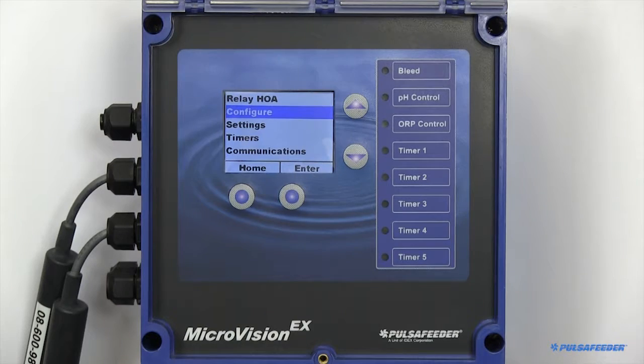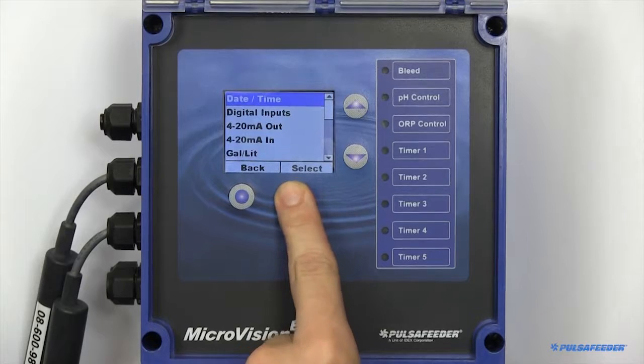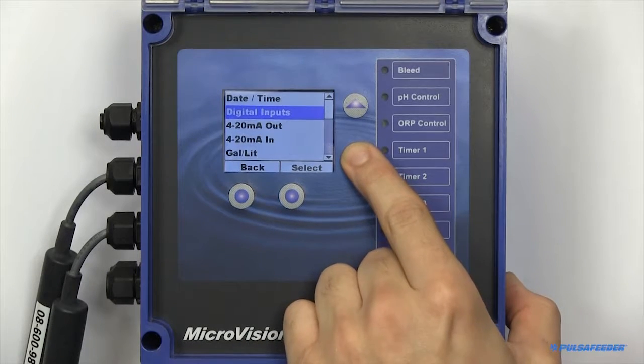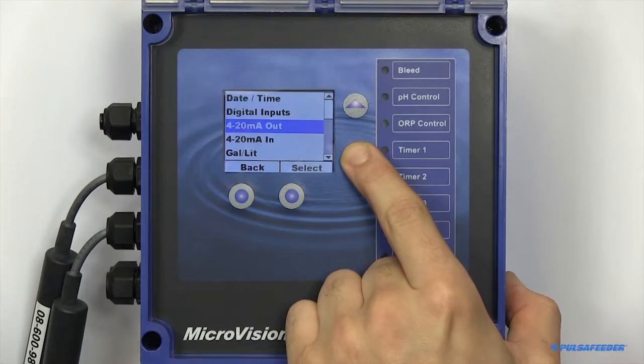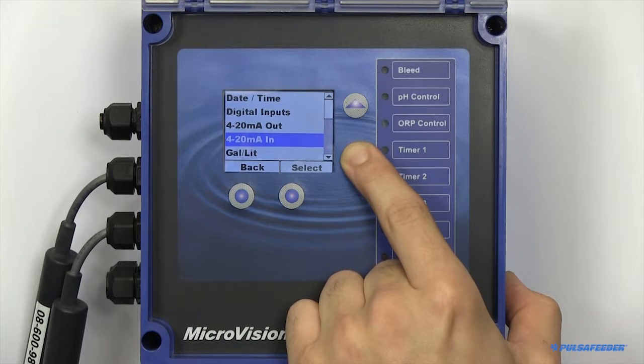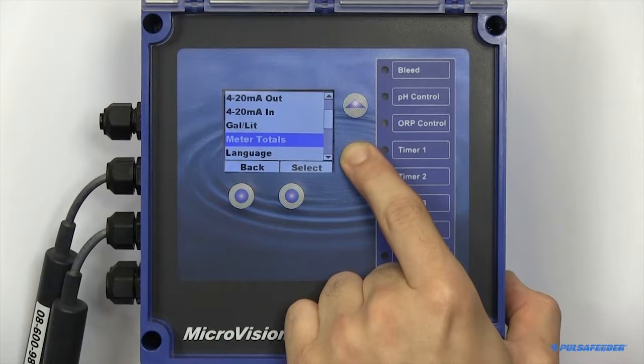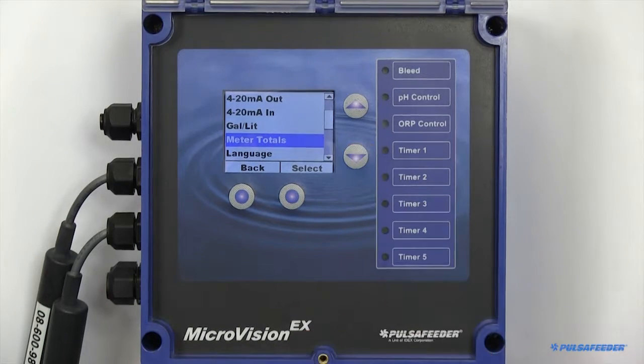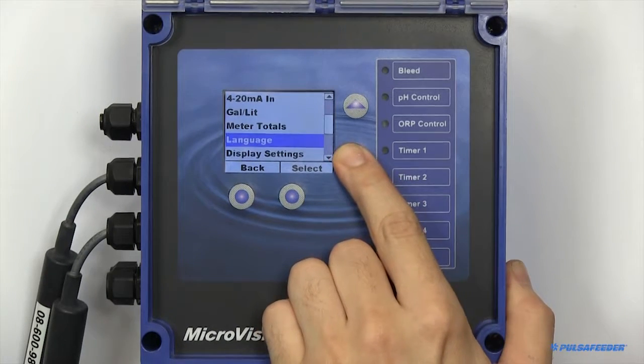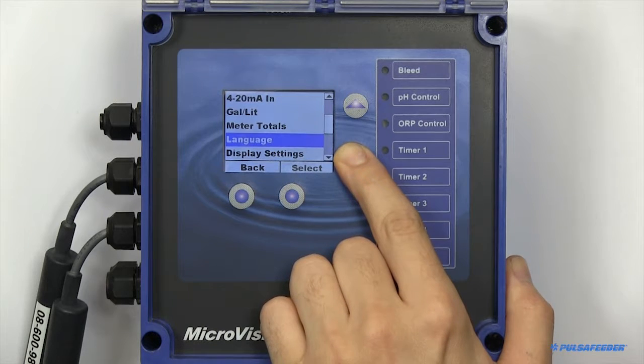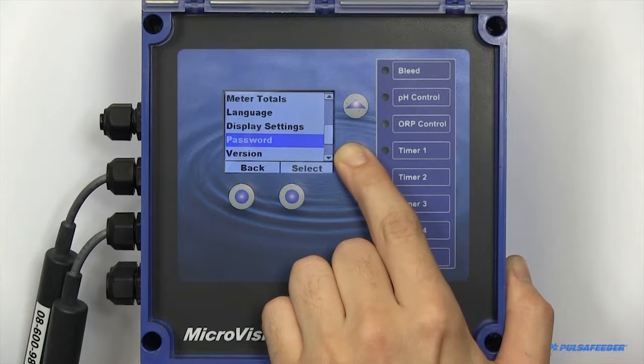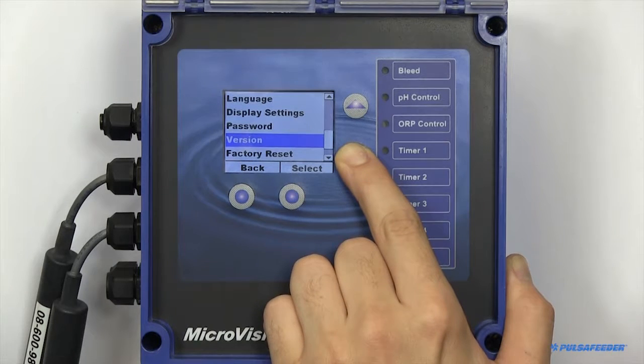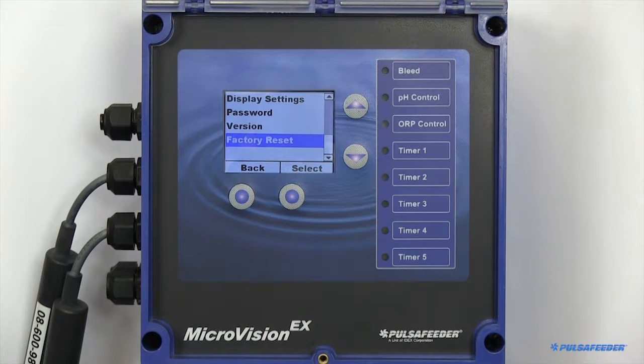The Configure menu is where you can access your date and time settings, adjust your digital inputs, enable or disable your 4 to 20 milliamp in and output functions, adjust your units, reset meter totals, change the language of the unit, configure display settings, enable software passwords, view the version of the software, as well as initialize a factory reset.